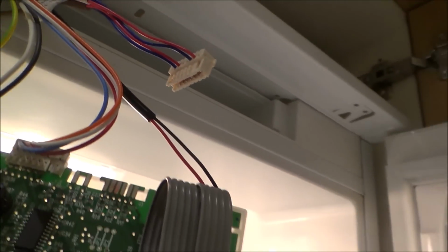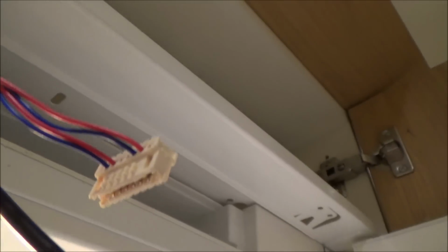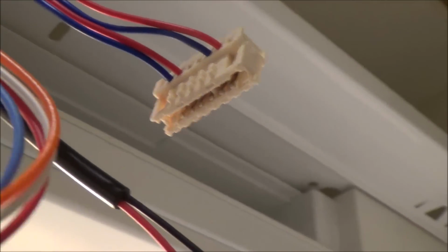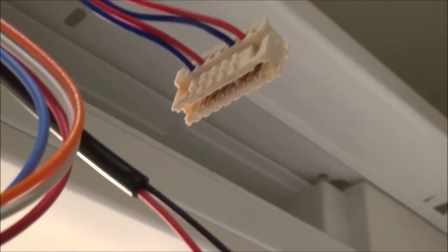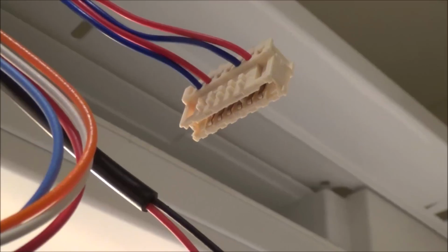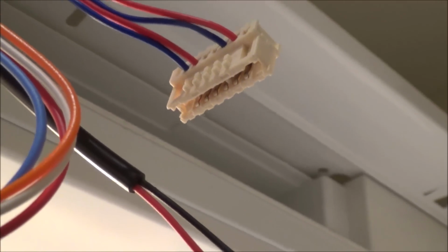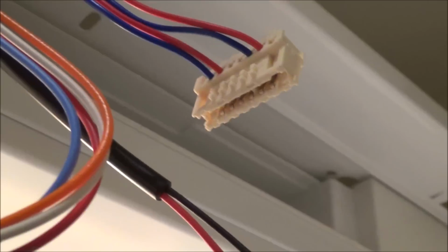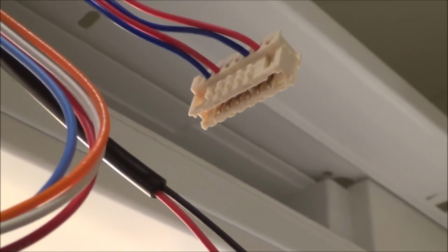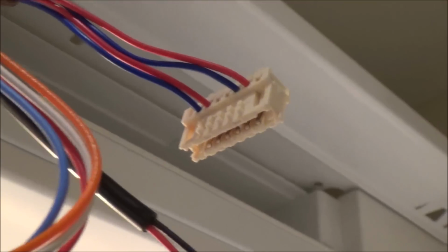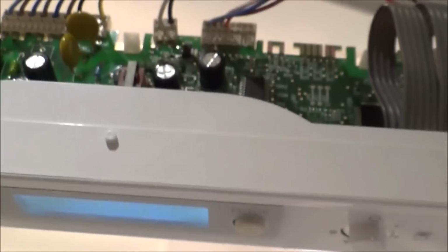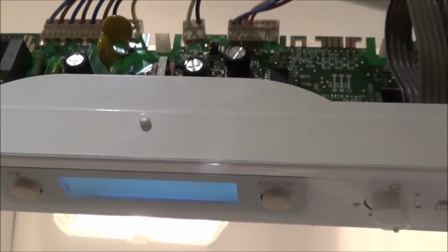What I've done is gone across the probes with everything dead, unplugged from the mains - this is all 240 volts - and it's showing ohms on both of them. When I open the doors, the values change, so as it gets warmer the values change. So I don't believe these are faulty, and I don't believe my old thermal cutout switches were faulty, or the new ones either. I can't see what other sensor it would be.